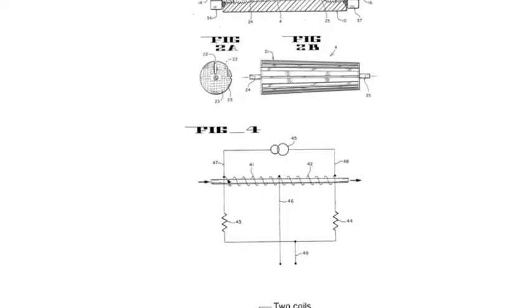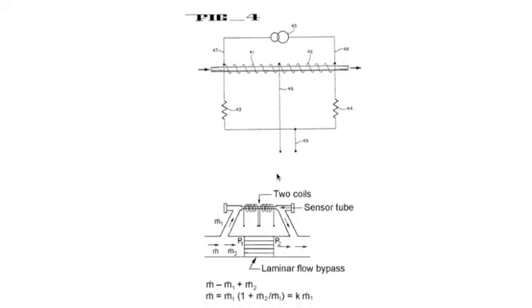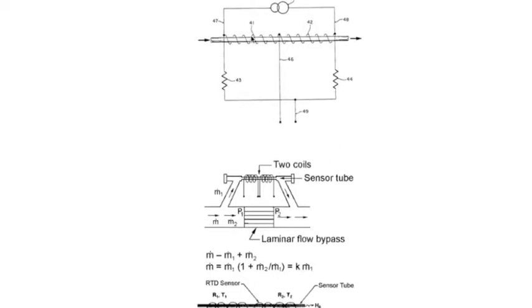This is an electrical representation of the sensor, where there's a winding across a hypodermic needle, center tapped, and we measure the resistance. We create a constant current through this sensor. And we're measuring T2 minus T1.